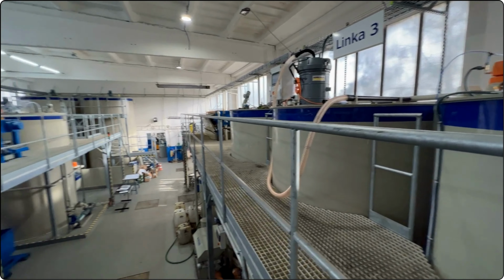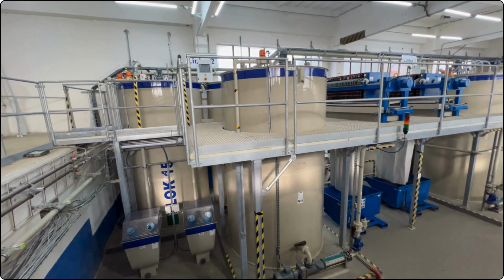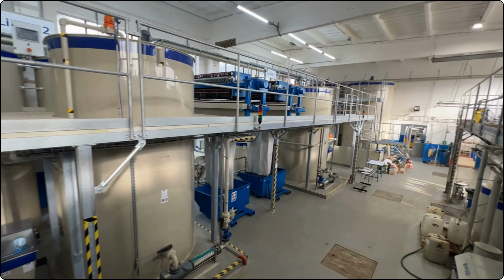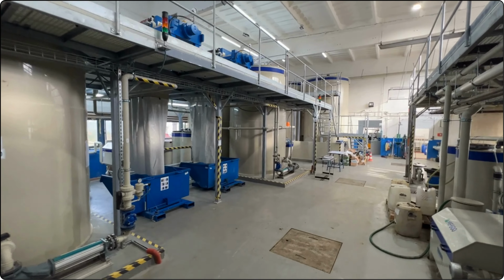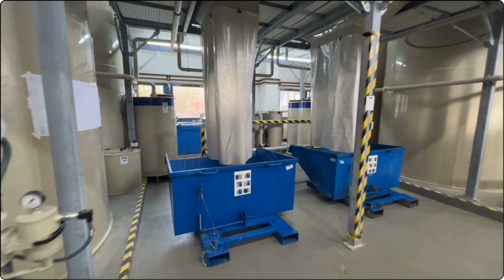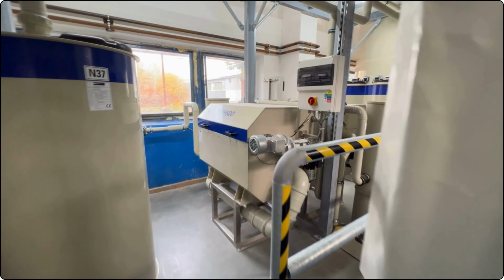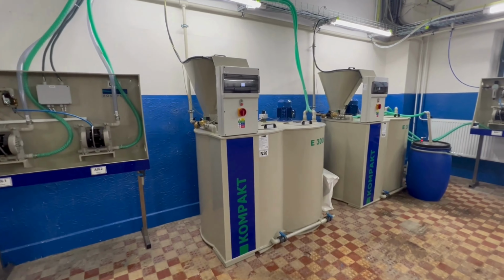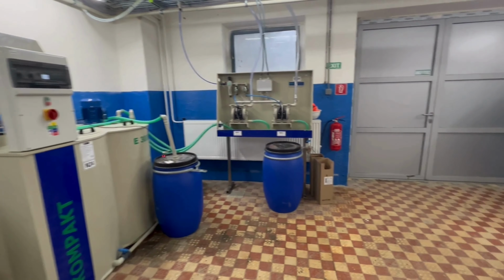After the chemical treatment in the reactors, the precipitated mixture is fully pumped into a separation reactor where the subsequent processing and separation take place. The dewatering of the precipitated sludge is provided by filter presses. The filtrate from the filter presses is collected in a pre-treated water storage tank. Chemical agents are dosed in liquid and solid forms. The preparation of solutions from powder takes place in automatic preparation units.